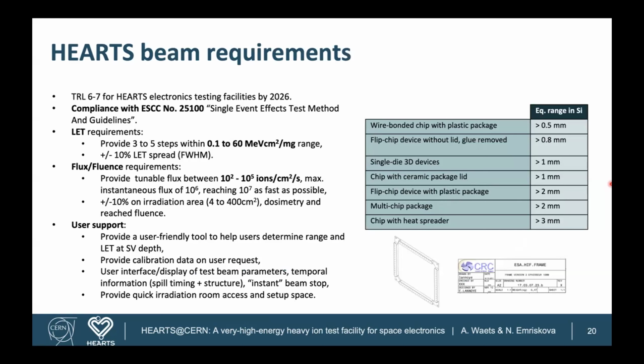And just a very, very quick word that within the project very early, we talked a lot about establishing, let's say, beam requirements, because the testing with very high energy heavy ion beams is a fairly new domain. So a document was made which, let's say, acts as a standard or as a protocol which exists already for single event effects testing in the form of ESCC or ECSC.